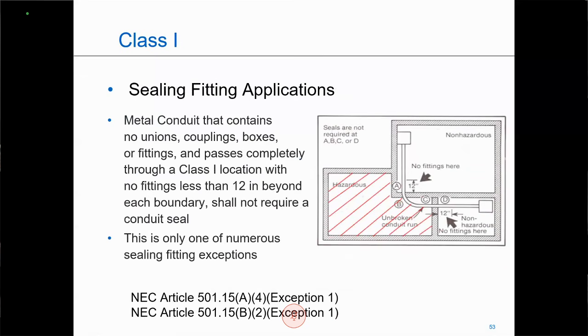Now, the boundary seal does have some exceptions. In Class 1, Division 1, there's this particular exception where if the conduit runs from a non-hazardous area to another non-hazardous area, completely unbroken through my hazardous area, and I'm at least 12 inches before there's any breaks within the non-hazardous area, I do not have to put a boundary seal here. There's nowhere for the gas to be able to migrate into the conduit here. There's no threaded openings, no couplings. So I wouldn't have to have a boundary seal.